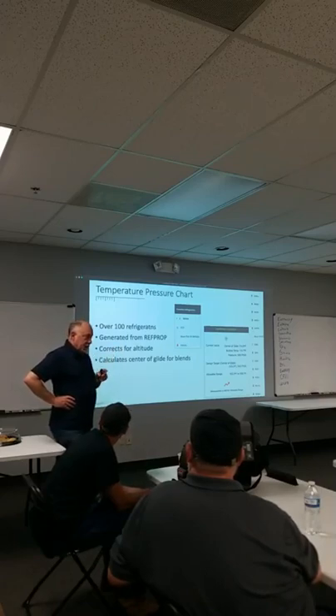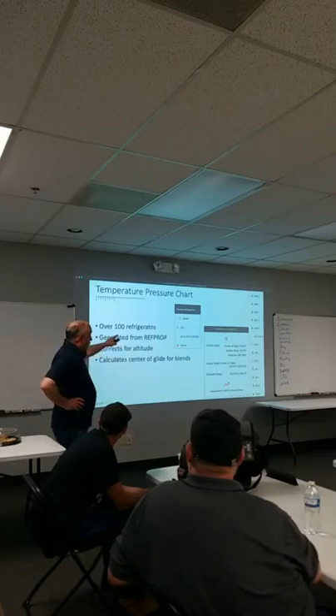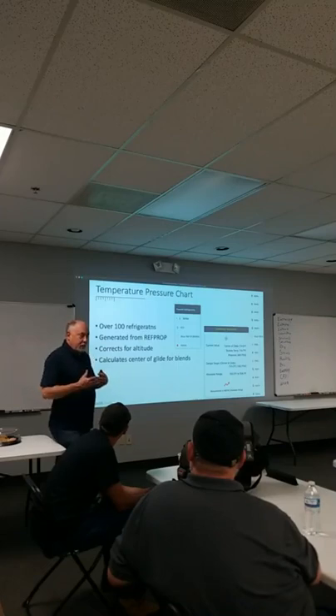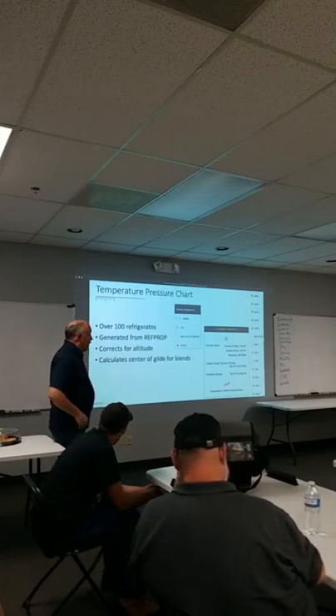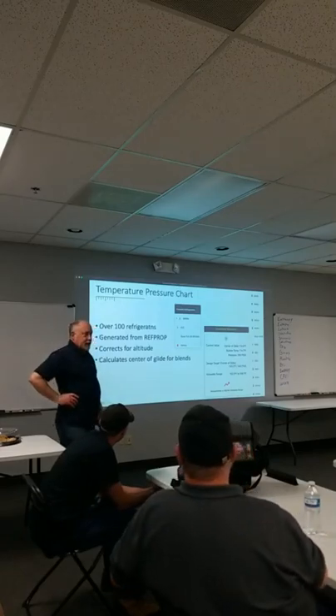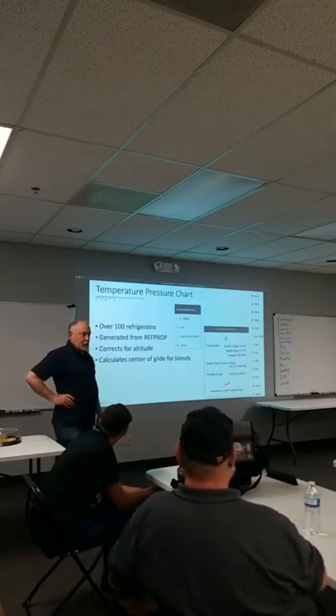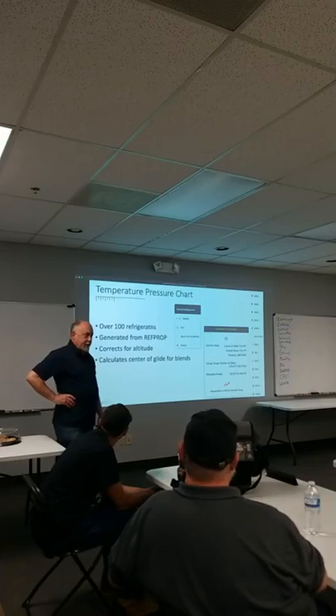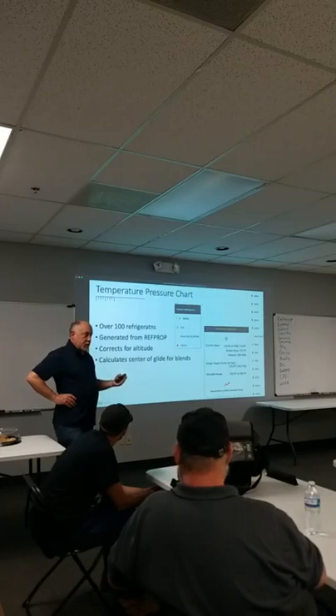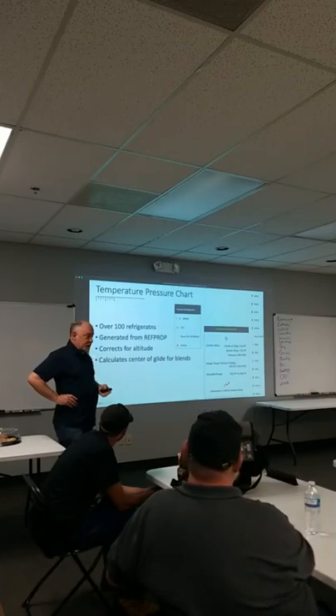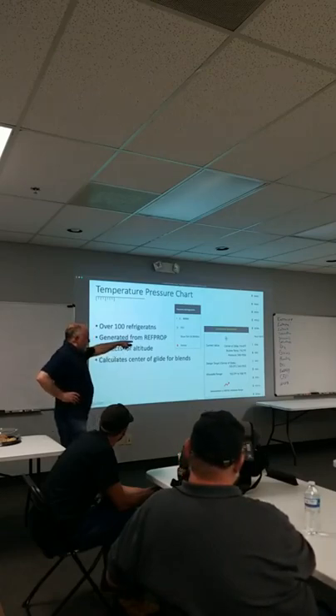Yeah. But our gauges are relative, right? So, one of the things that Measurequick does that's unique, that you gotta watch, like if you go into set up a Fieldpiece gauges, a lot of people get the gauges and look at the temperature pressure relationship. And we have a refrigerant that has bubble point and dew point. Now, I always remember this, cause I always get this confused in my head, so I always tell people, remember it as dew for heat and bub cooling, alright? Just if you don't remember, dew point is for superheat, and the bubble is for subcooling, when you're doing your subcooling calculations. You can see that Measurequick calculates the center of the glide.